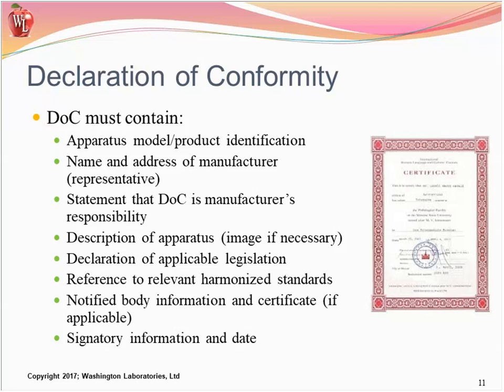2014/30/EU with product standard EN61326-1 and EN61326-2-1, whatever is applicable here. The dates of it, the declaration of the legislation, the reference to the standards, and any notified body information and a certificate if it's applicable.